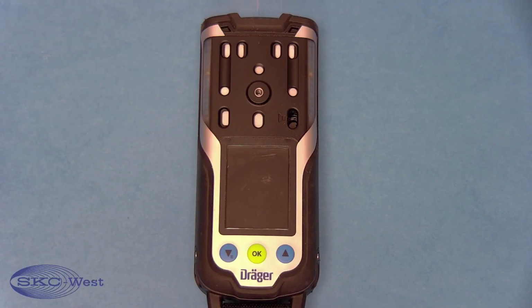Today we're going to be going over the Draeger X-am 3500 and the Draeger X-am 8000. Both of these instruments are in the same case, so the buttonology and function is quite similar. The X-am 3500 is a multi-gas detector, usually with a setup of the standard 4 gas sensors. The Draeger X-am 8000 is a multi-gas detector with a PID option, infrared sensors, and various toxic sensors as options. Ours is set up as a standard 4 gas plus the PID.